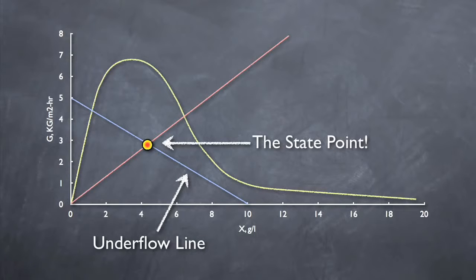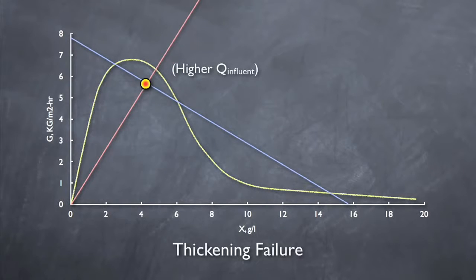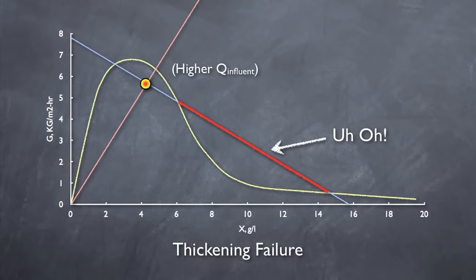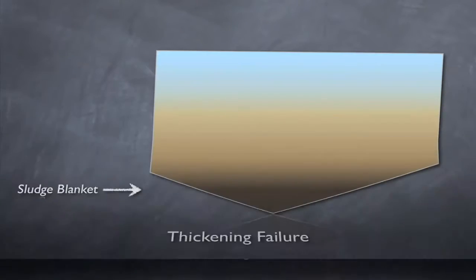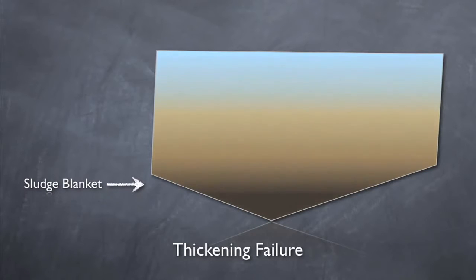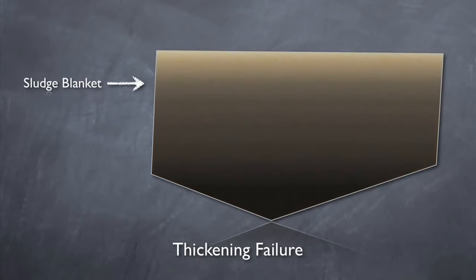If the state point is under the curve, but the entire underflow rate line isn't, the clarifier is failing in thickening. This means that sludge is settling in the clarifier, but isn't being removed fast enough. Under these conditions, the sludge blanket would rise in the clarifier until solids are passing over the weir.